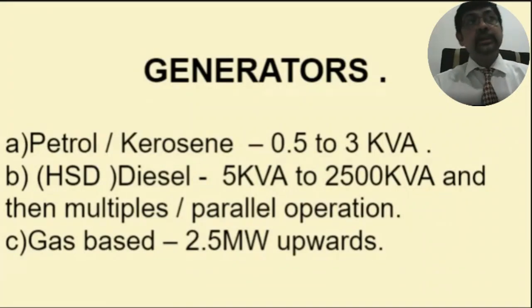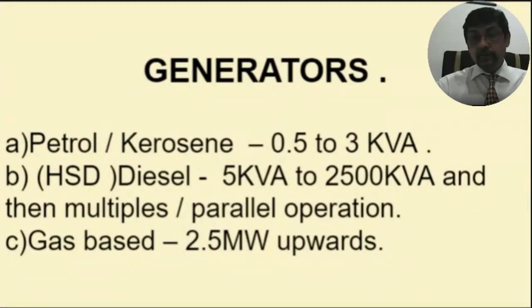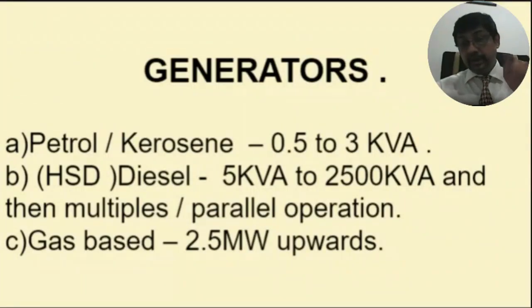Initially, imported generators had the upper hand somewhere in the late 90s or around 2000. We had LDO generators also, but they consumed a huge amount of space and were not easy to maintain. Whereas these diesel generators, 5 kVA to 2500 kVA and multiples: if a factory or industry has a requirement of, say, 4000 kVA, they can go for 2 of 2000 kVA. If a factory requires 6000 kVA, they can go for 1500 kVA into four numbers, that is multiples or parallel operation.